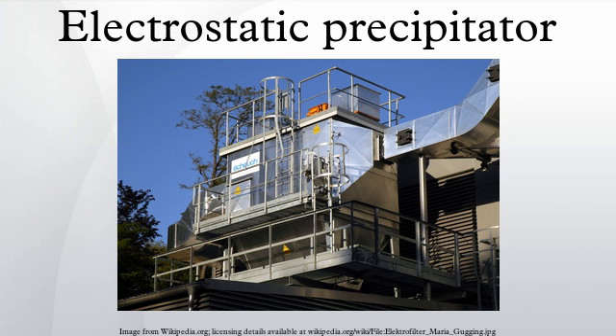Resistivity, which is a characteristic of particles in an electric field, is a measure of a particle's resistance to transferring charge. Resistivity is a function of a particle's chemical composition as well as flue gas operating conditions such as temperature and moisture. Particles can have high, moderate, or low resistivity. Bulk resistivity is defined using a more general version of Ohm's law, as given in the equation below, where E is the electric field strength, J is the current density, and ρ is the resistivity.